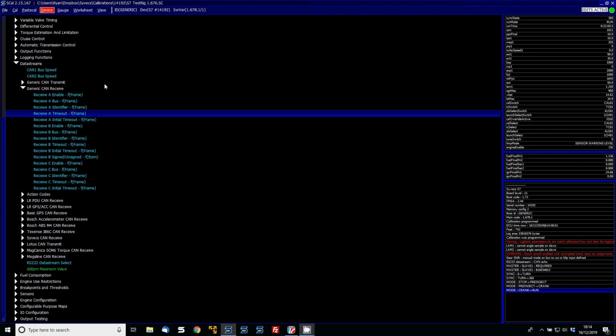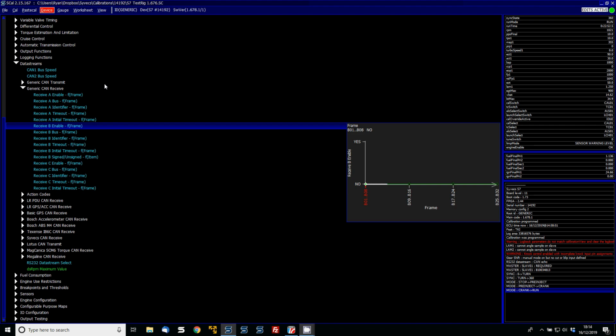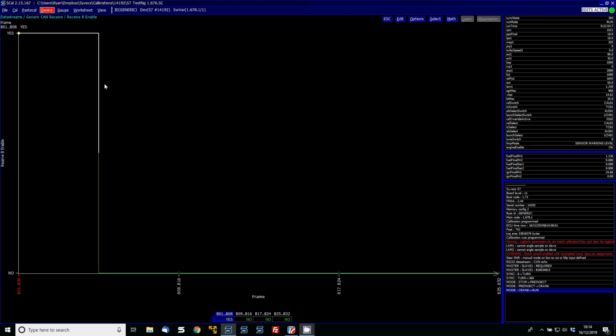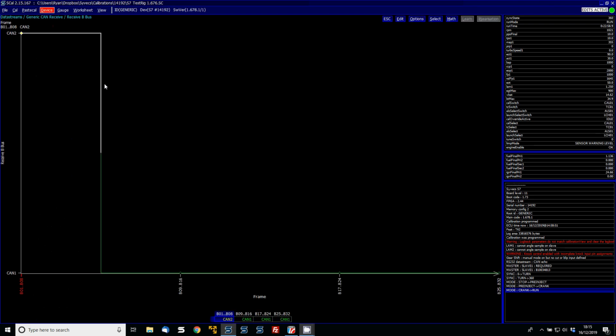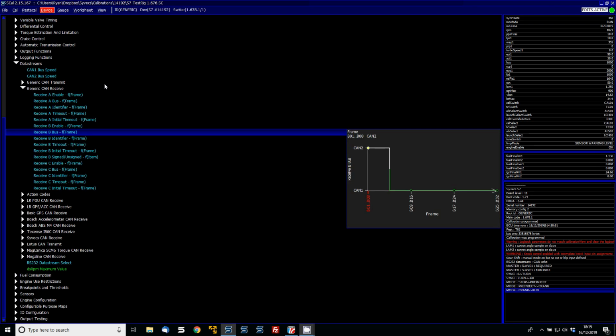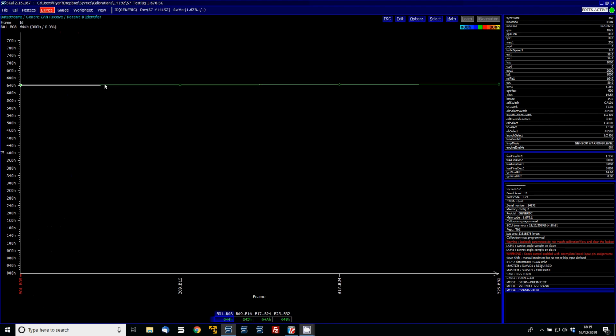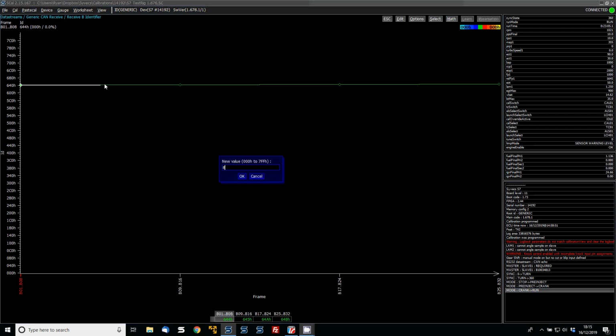So what we're going to use is receive B, and we're going to set yes to receive B on B1 to 8. Then we're going to set the bus to be CAN 2, because that's what we're connected to on this S7 for the PDU. And the identifier was 718H. The H at the end needs to be input to tell it that it's in hexadecimal.